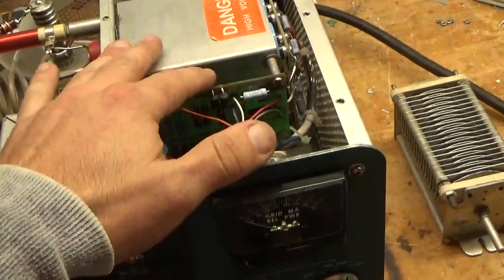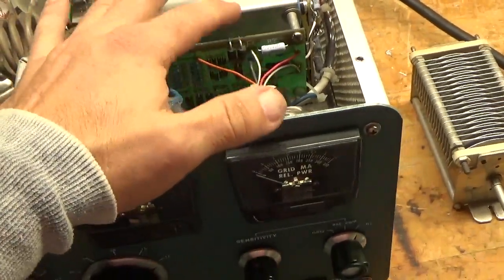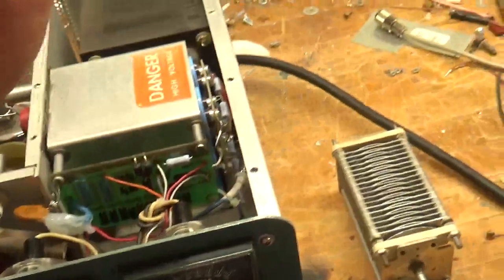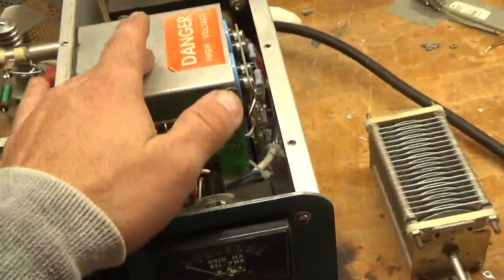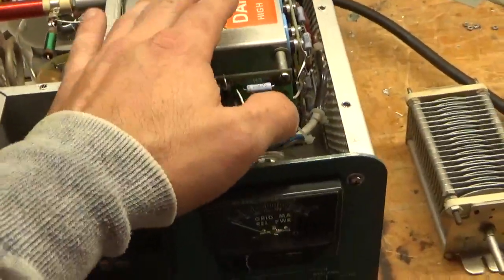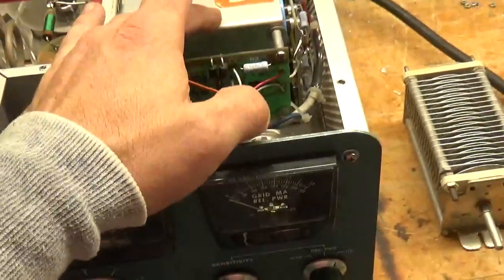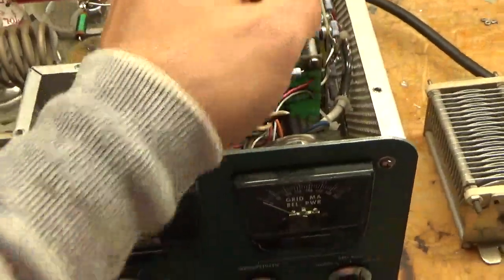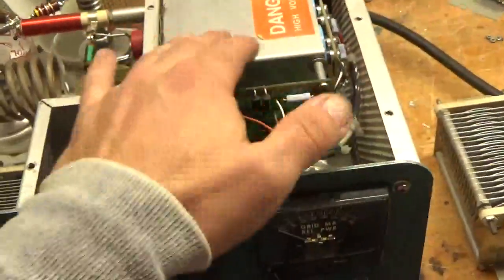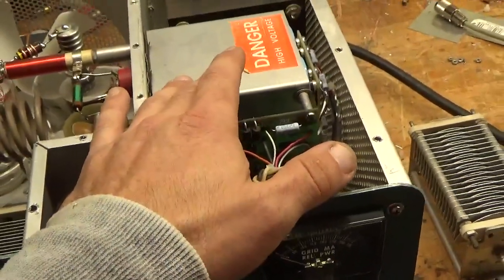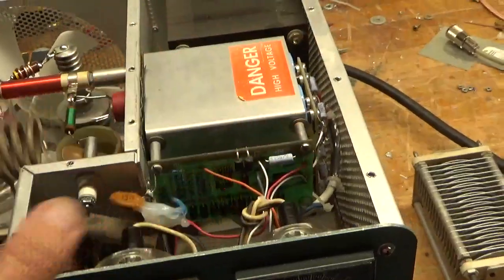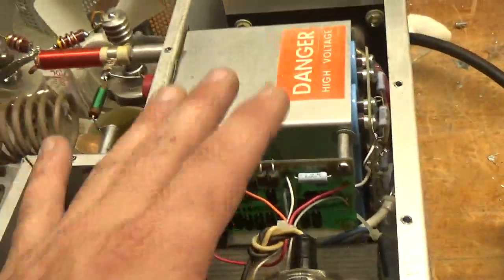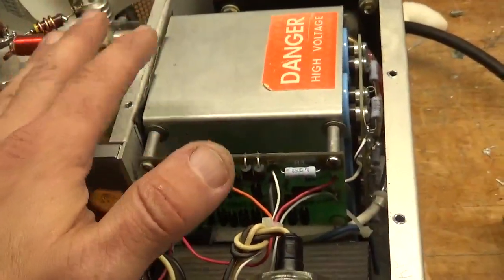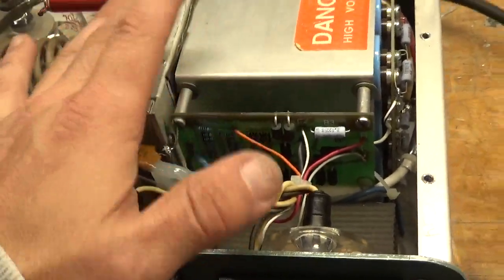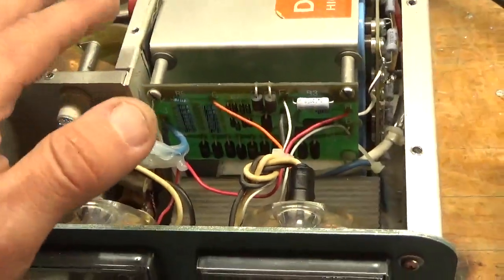Had the Harbach filter board kit in here, metering board kit, fixed some solder connections, fixed the secondary high voltage lead. It's done properly with high voltage wire, heat shrink doubled up, and then silicone tube over that, so it's like overkill. That thing will never have an issue. Connected, soldered, all that, so we'll never have a connection issue or any sort of arcing issue there. First time I've ever had to do that. I've never seen someone do that before.